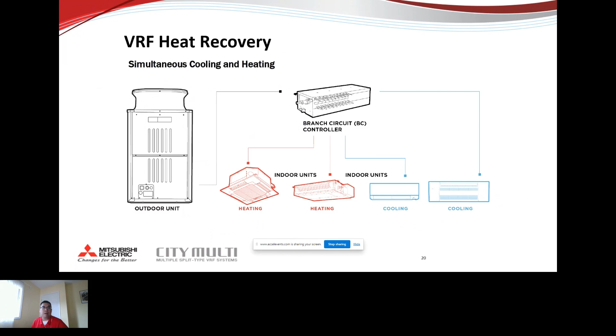But coming back, another thing is, now we do effective heating and cooling, but we also want to do zone-to-zone ventilation, right? Because people need fresh air to be awake, alert, and productive. But again, even within our own office, some people come to the office at 6 o'clock, and me personally, I go at 9 o'clock. So that's a 3 hour difference between when they are in the office and when I'm in the office. So turn off the lights, and maybe the unit will also be able to switch to low CFM depending on which zone you are in. So that is kind of on-demand ventilation, as well as time schedule on the ventilation side of things, to reduce how much fresh air really needs to be treated.